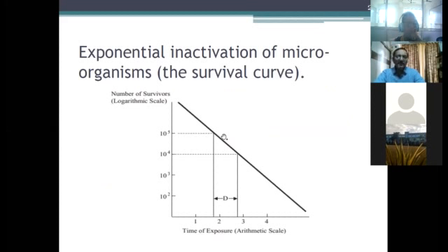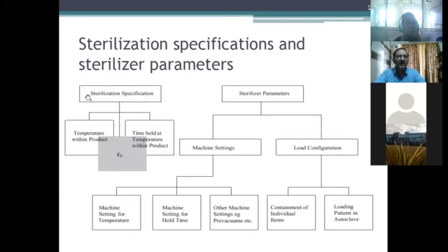So as you know, this is about the D value, and D value is the time required for 1 log reduction in the microorganisms. Okay. So here you can see the sterilization specifications and sterilization parameters. The F value is calculated from the temperature in the product and the time for which the product is held at that temperature. So these two things are important. From this you can calculate the F value, and it can be done electronically also, and it can be displayed on the modern autoclaves. You can see that the F value is 5, 6, 7, 8. It is slowly increasing. You can reach the required F value, and then you can stop the sterilizer.